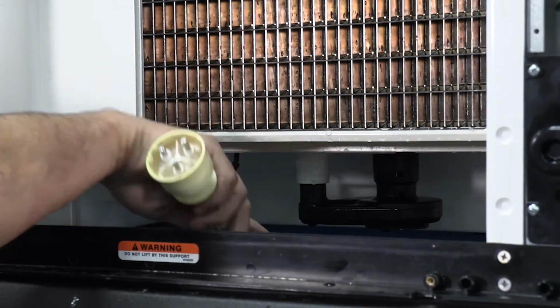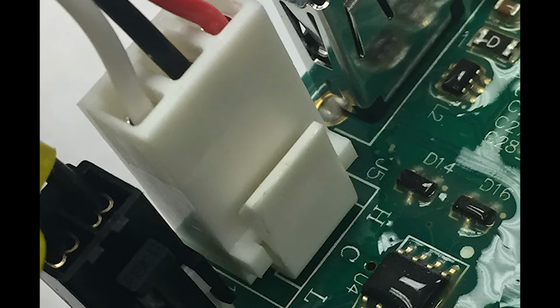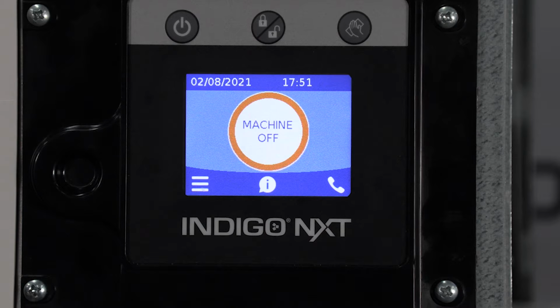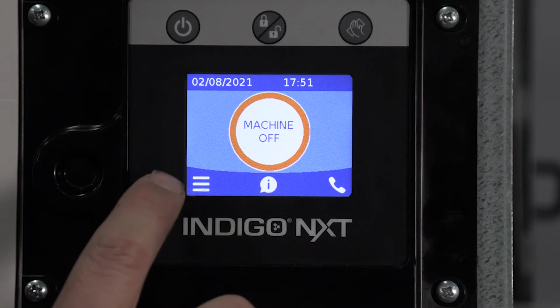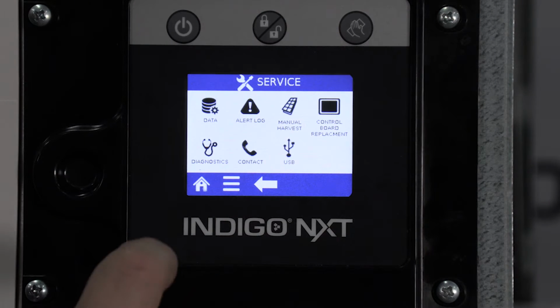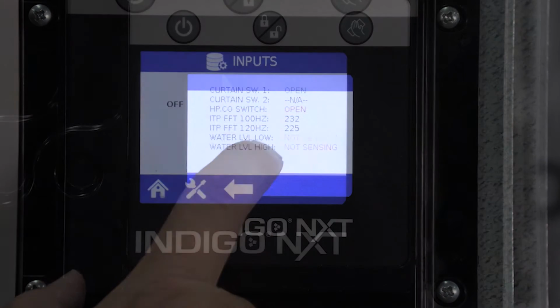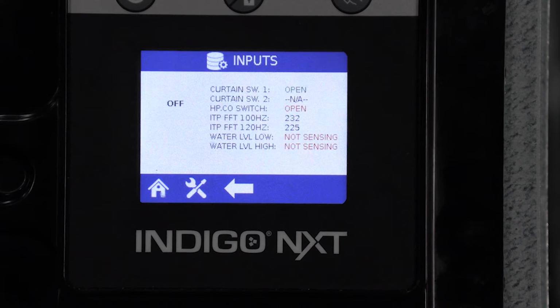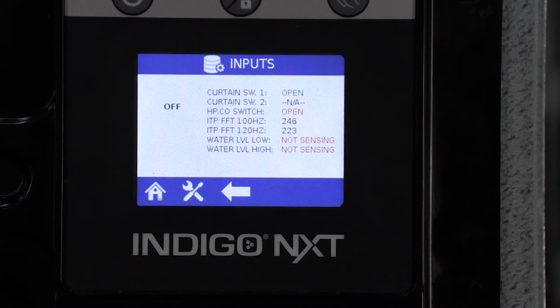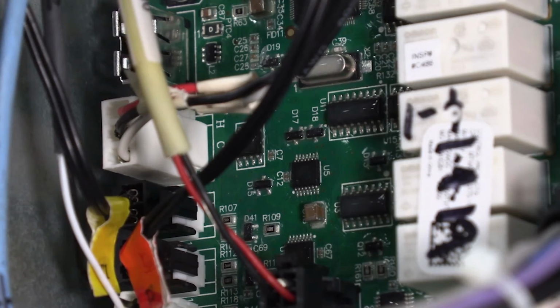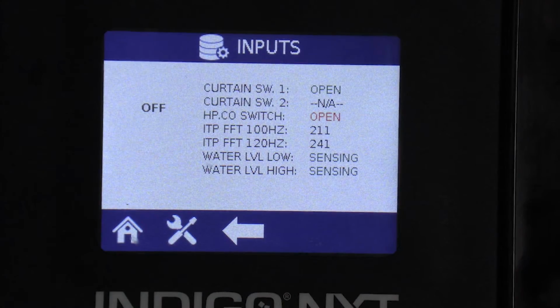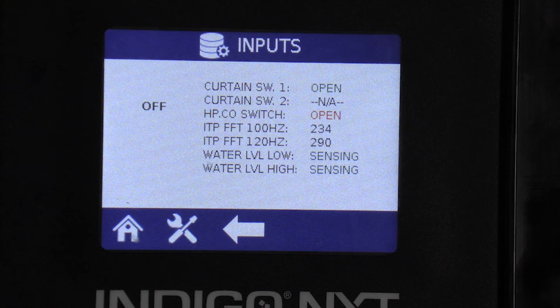Step 2. Check water level probe mounting and verify the wiring connection at the probe and the control board is secure. Step 3. We're going to navigate to the input screen. So we're going to press Menu, Service, Diagnostics, and then Inputs. And we're going to view water level low and water level high on the display. If not sensing is displayed on both water level low and water level high, and the water level probes are touching water in the water trough, then the water level probe is not conducting properly, or the control board is not receiving the signal. If sensing is displayed, control board is receiving a sensing water signal.